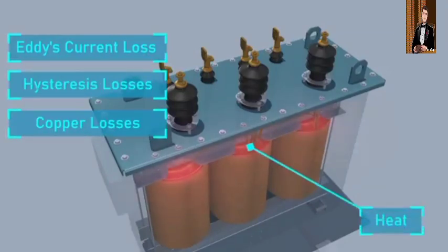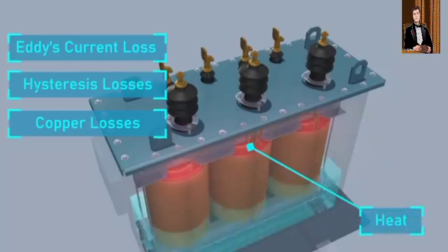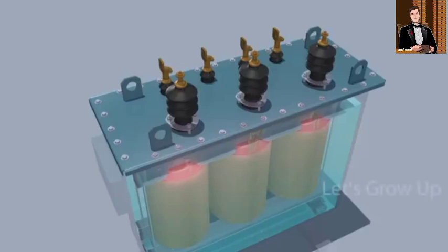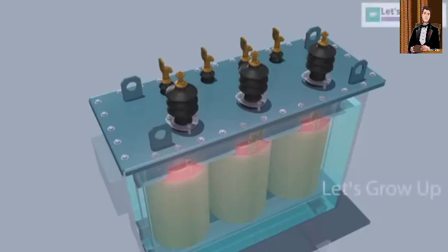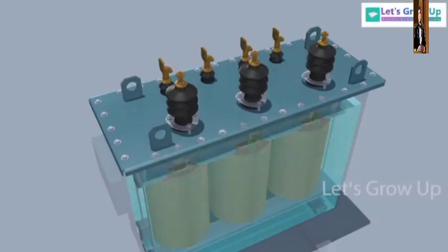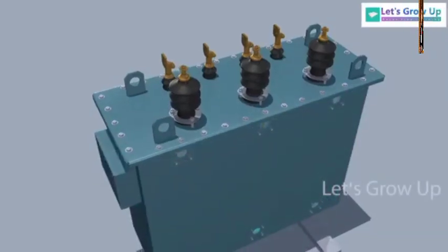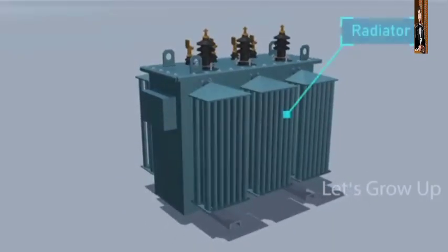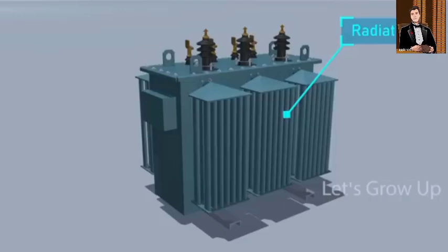To prevent heat, transformer oil is used inside the tank. The main role of transformer oil is to act as a coolant and to insulate. Transformer oil is an exceptional heat conductor, and can effectively reduce the copper coil's temperature, stopping them from burning. Not only that, external cooling tubes, or radiators, are there. The radiator of the transformer accelerates the cooling rate, so it plays a key role in increasing the loading capacity of an electrical transformer.